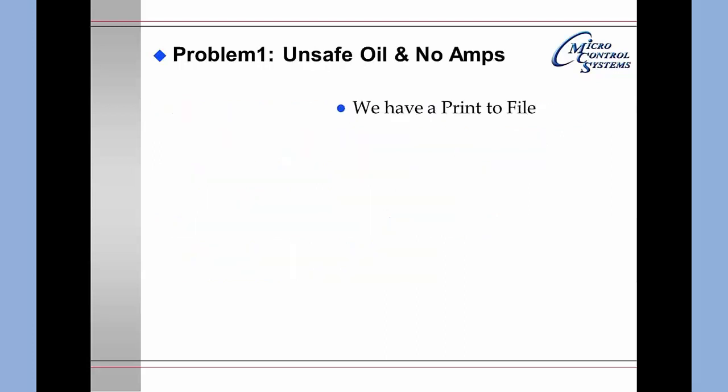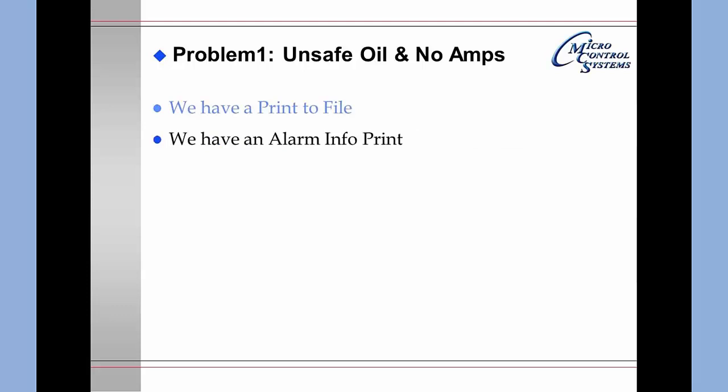Unsafe oil and no amps. We have a print to file which, as mentioned, is a spreadsheet of the current status within the Magnum. We also have an info screen printout from an alarm showing the unsafe oil and no amp status just prior to its occurrence.